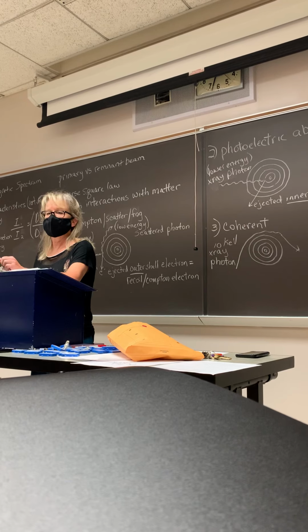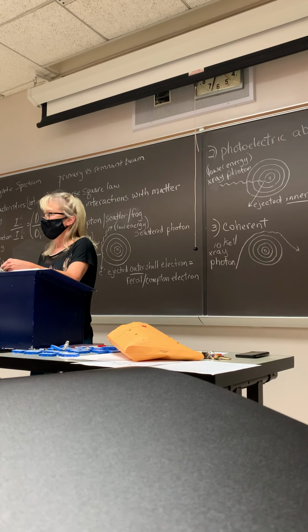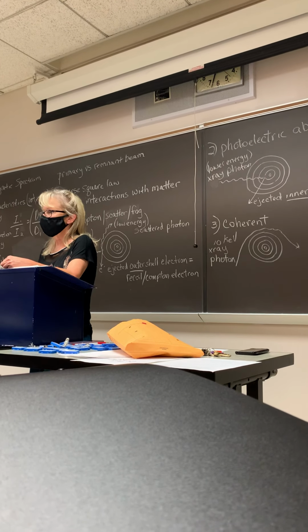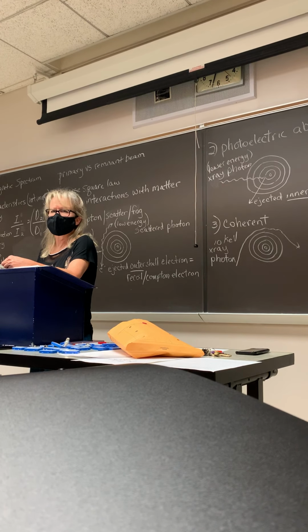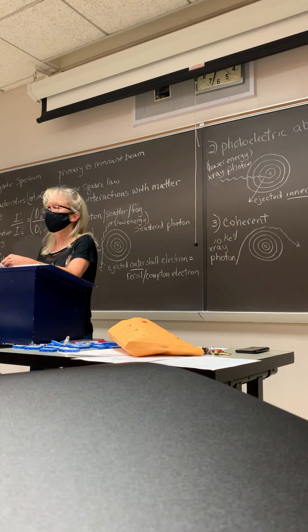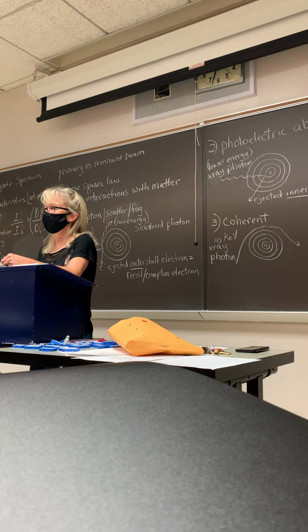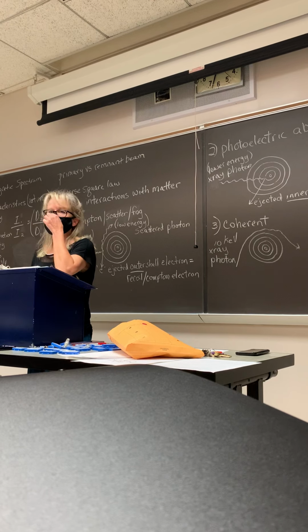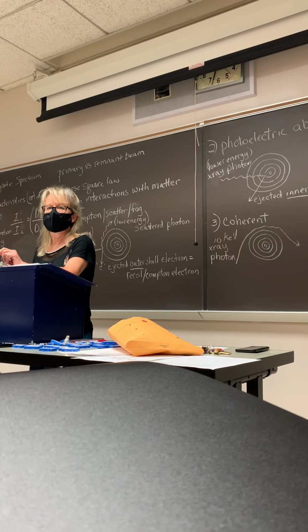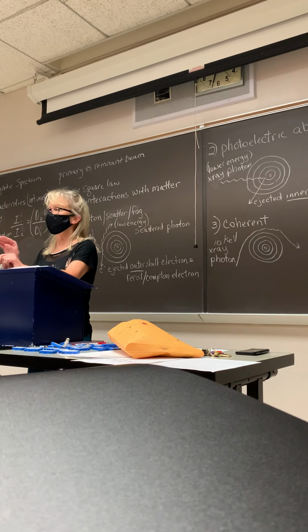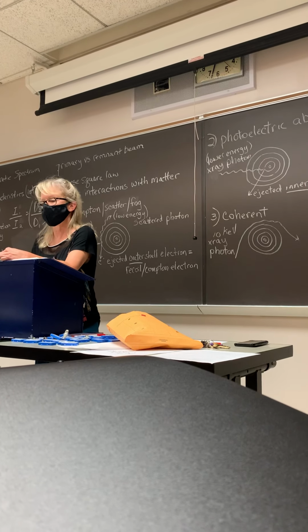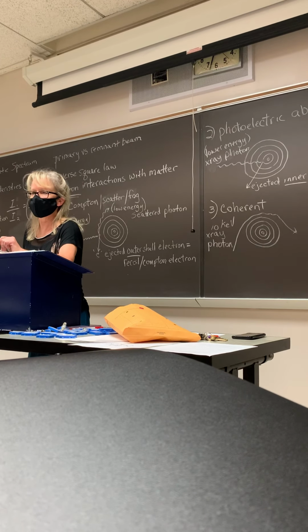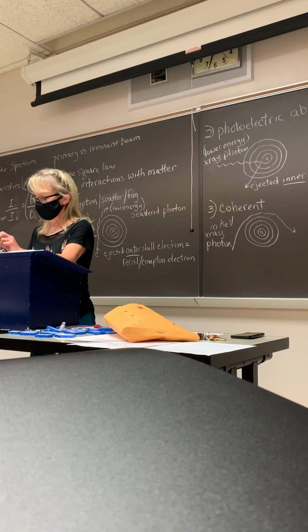Okay, for fluoro, as far as the patient dose is concerned, the best fluoro machines are the pulsed digital ones. You guys seen them out there? The other groups said they've never seen the pulse fluoro. You've never seen? I thought the VA had one. Anyway, you can almost kind of see it pulsing like that. So that's the best one as far as patient dose is concerned. It's a decrease in patient dose.